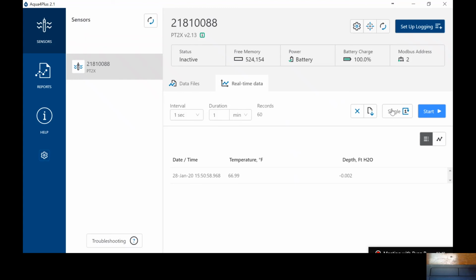It's never going to be exactly 0 because there is water on top of the sensor at this point, but we should still be about 0. And take a couple readings, make sure everything looks right. Temperature looks normal. The best thing to do, if you're sending out more than one sensor, is to compare the sensors and use the same cup of water. They should be reading just about the same thing on temperature and on depth.